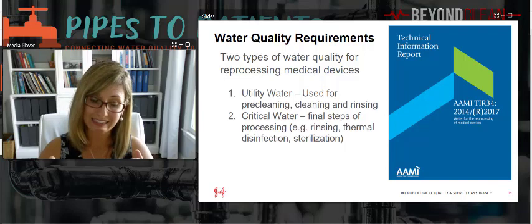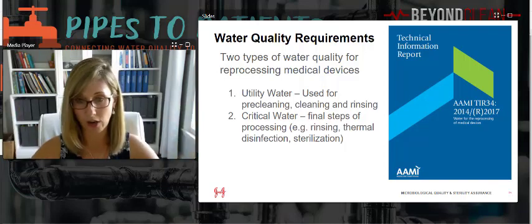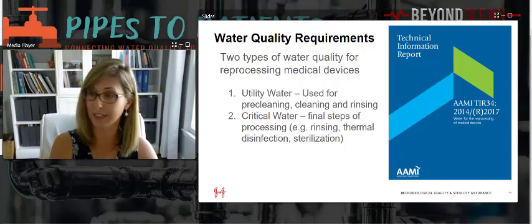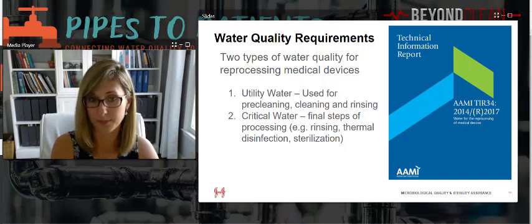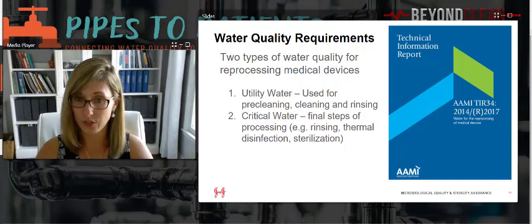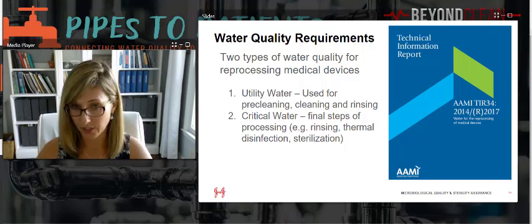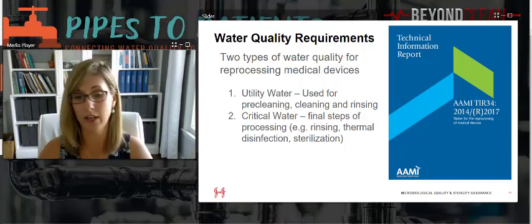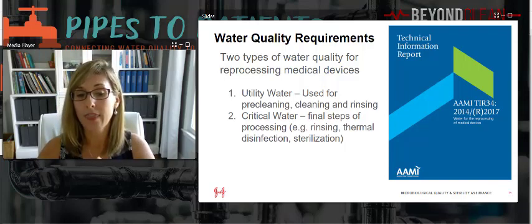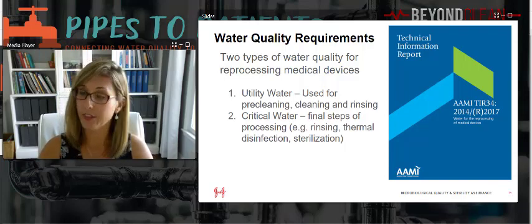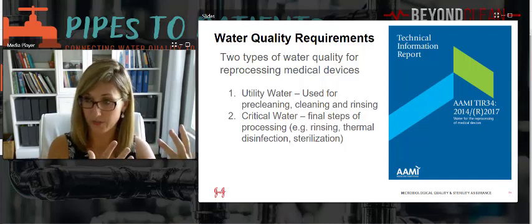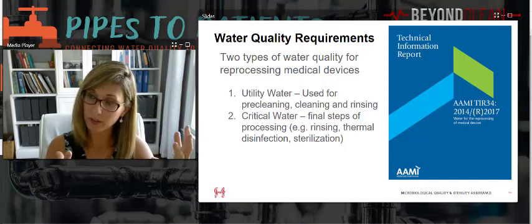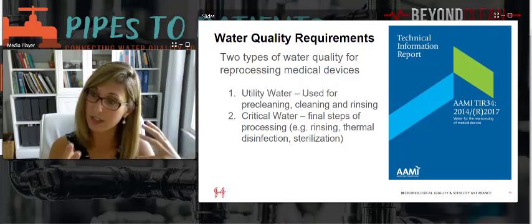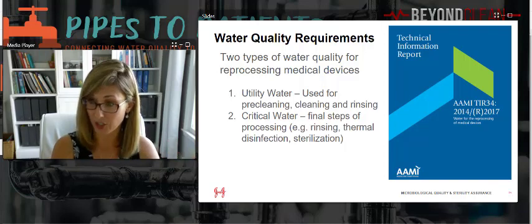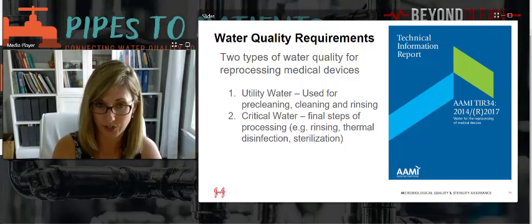The reason is that clean water shears off anything that may be residual from the poorer quality utility water used earlier in the process. So in addition to the rinsing steps that could be in a washer disinfector, manual, or in an AER, that water is also used within the thermal disinfection phase of the washer disinfector, where we're heating the water to a temperature point that facilitates disinfection of microorganisms as part of that cycle.